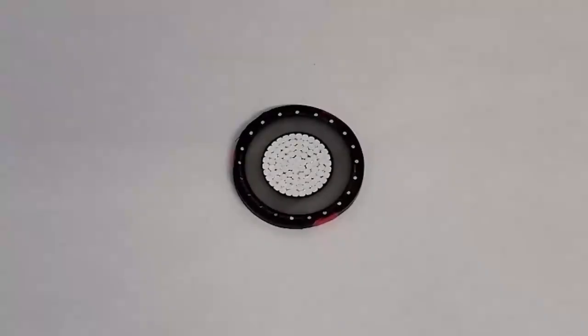Hey YouTubers, today I wanted to talk about some underground medium voltage cable. So what you see here is about a 3/16 inch thick wafer of a 35 kV cable. When I say 35 kV, the insulation is rated for 35 kV, but that's three phase. So single phase, what you actually have running through this is about 19,900 volts to ground.